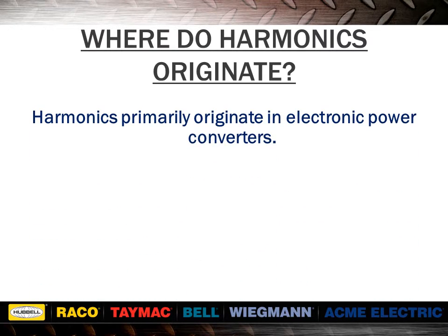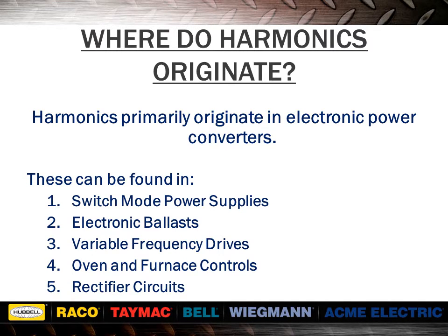Harmonics primarily originate in electronic power converters. These can be found in switch mode power supplies, electronic ballasts, variable frequency drives, oven and furnace controls, and rectifier circuits. Harmonics originate any time current is being drawn in short, rapid pulses rather than in a smooth, continuous manner.